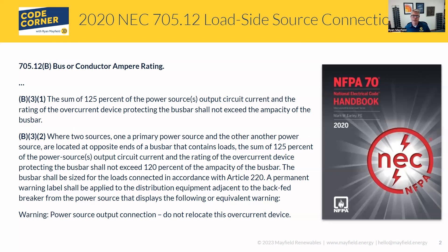So we're going to take 125% of that total value. If your inverter puts out 32 amps, you take 32 amps times 1.25, which is exactly 40 amps. That calculation applies in both B31 and B32. B31 says if that value plus the overcurrent protection device from the utility — if those two added together don't exceed the ampacity of the bus bar — you can put your interconnection point anywhere on the bus. There's nowhere along the bus bar that will see more current than what it's rated for.